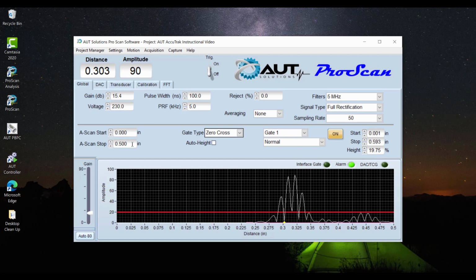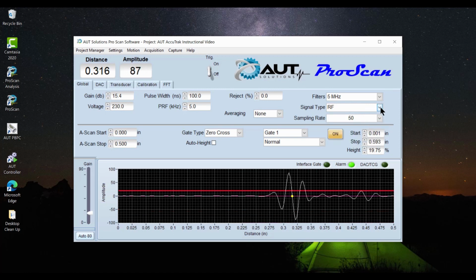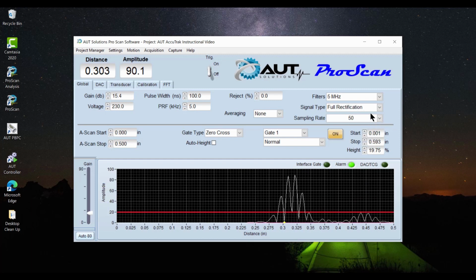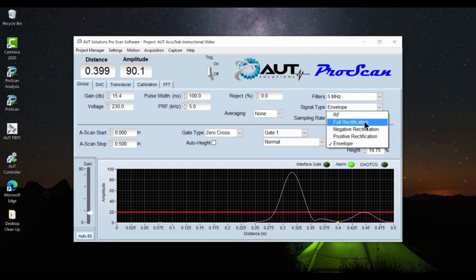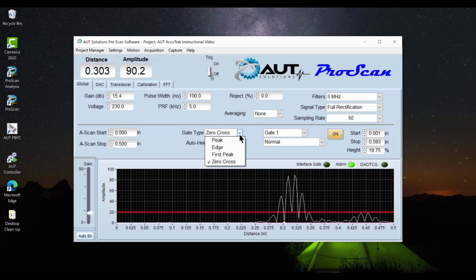So if we have a decrease in wall or any blisters on the inside, we'd be able to see that additional information down to a 1/2 inch. So we're going to go in. We got our filter set for a 5 meg probe. If you were running a different probe, you would simply come in here and select it from the drop down. You also here have the ability to change it into an RF signal, your fully rectified signal, which is what we typically scan on. You have negative rectification, positive rectification, and your envelope. So we will go fully rectified as we're running our gate on 0 cross.